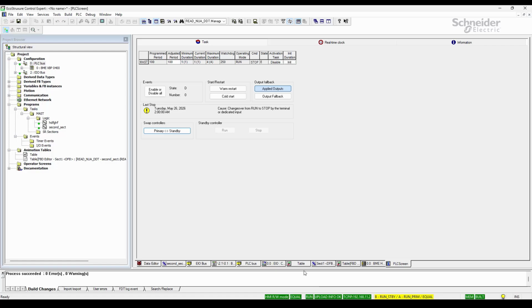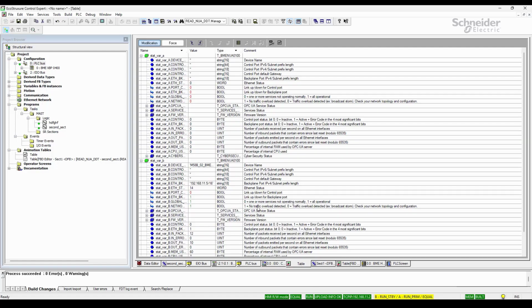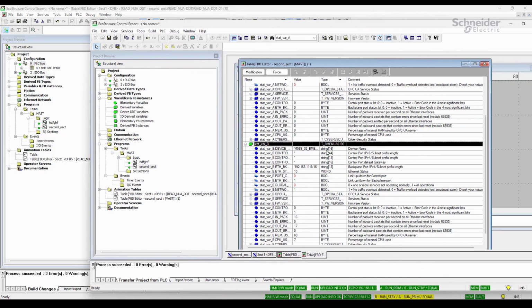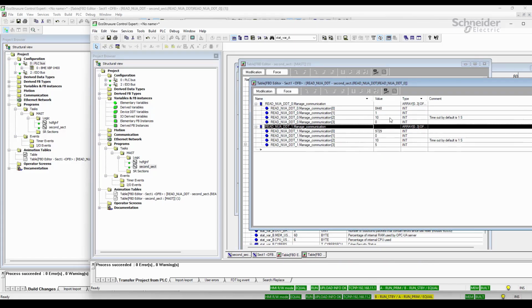So the swap has been done, and if I bring the table here, we see that this is still updating correctly, and now this is no longer moving because now it's the standby, and the values are not being exchanged. Here, this is the new primary. We see the values being updated here, and then this one now gets a transaction number updated and everything.